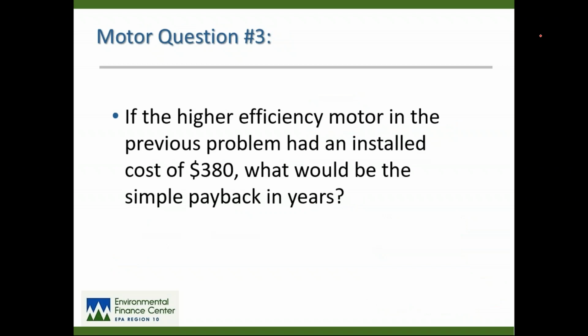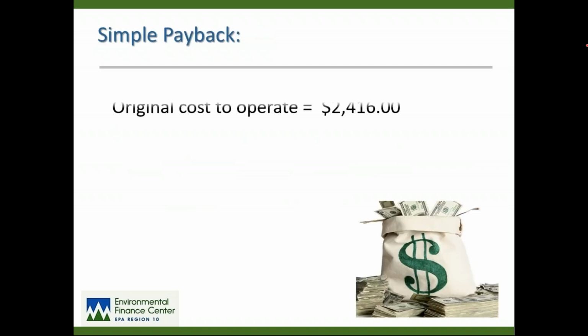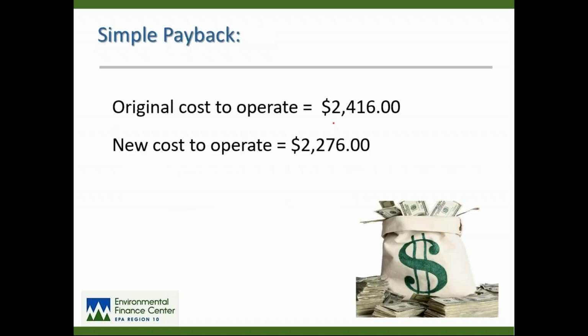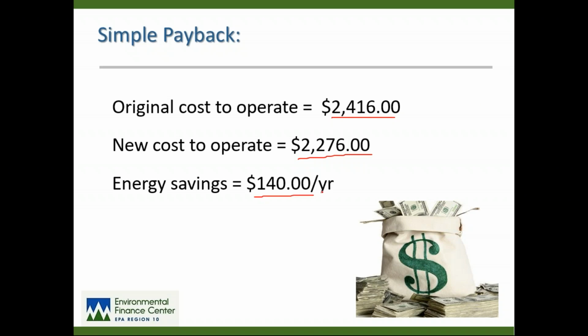So the bottom line is, what do we want? What is that payback going to be? How many years is it going to take to pay us back for that motor in energy savings? So let's say that motor had an installed cost of $380, which is pretty typical for a 10 horsepower motor. What would be the payback? Again, run the numbers. The original cost to operate, the new cost to operate with the premium efficiency motor. So we're saving $140 a year. Remember that that motor costs us $380 divided by 140. That gives us a simple payback of less than 3 years.